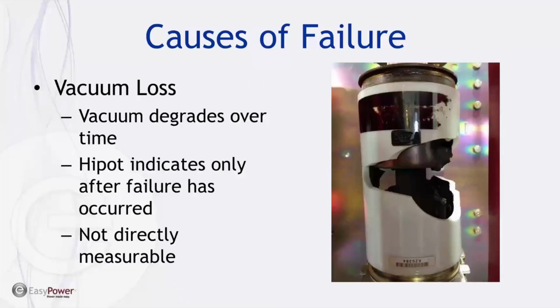So what we're interested in today is vacuum loss. Over time, the vacuum inside of a vacuum interrupter degrades. It doesn't matter how well you seal it, the vacuum will still degrade over time. The one thing that most people think about is gas permeation from the outside. Even though this container is made of stainless steel and ceramic, it is still possible for gases to diffuse through those materials, mostly very, very small gases like hydrogen or helium, which can have some effect on the vacuum interrupter if there are issues, such as a long path leak through a braze seal or something of that nature. But generally, gas permeation doesn't cause the failure of the vacuum interrupter.